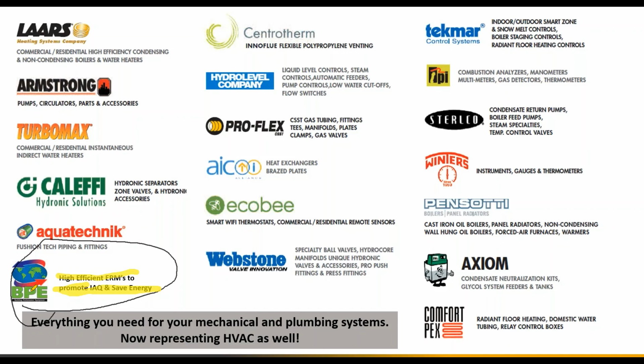And that's really how in Germany and in Western Europe they were able to comply with those strict requirements, with those lower temperature heating requirements: they increased the insulating value of the building envelope, and then put the panel radiators, typically underneath the windows, in those areas where you have your major heat loss, to compensate for the negative draft temperature effect of the window. The beauty of a panel radiator is that it provides both convective as well as radiative heat, they're very easily controlled, and they're available in a wide range of sizes.